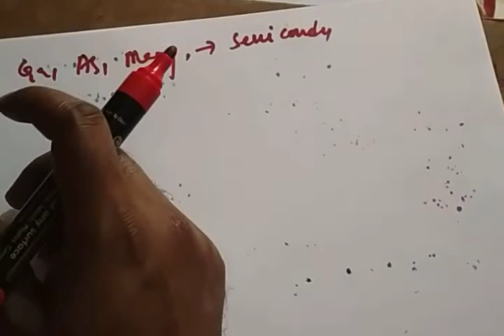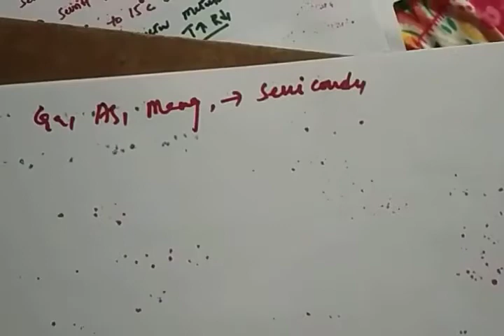I hope it's clear. A thermistor basically has a negative temperature coefficient, meaning as temperature increases, the resistance value reduces. For a small change in temperature, there's a large change in resistance value. Because of this, the sensitivity of thermistors is very high compared to RTDs. The materials used are semiconductor materials like gallium, arsenic, manganese, because these have negative temperature coefficients.